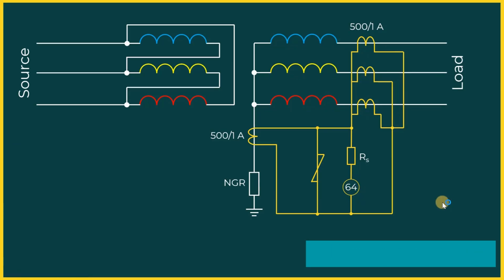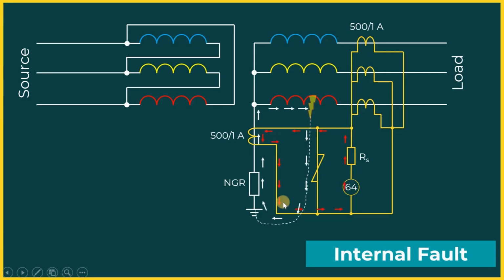Now imagine an internal earth fault occurs in the LV winding of the transformer. Under this condition, these white arrows show the current flowing through the transformer winding, and the red arrows represent the current flowing through the protection circuit. We can see that there is no current through the phase CTs, but there is current through the neutral CT. And this imbalance current will flow through the REF relay.